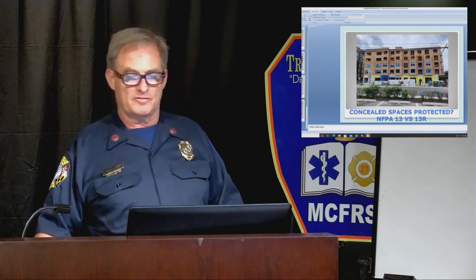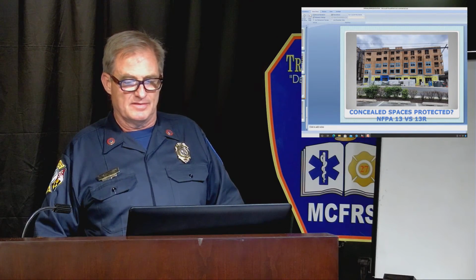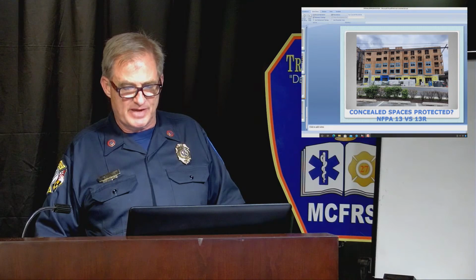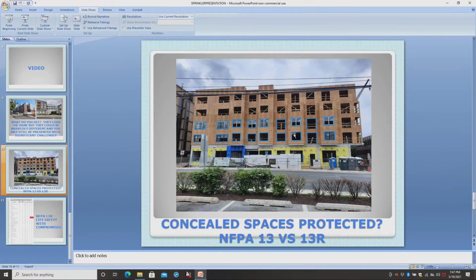Okay, so let's go back and look at our wood building. If we were to roll up to this building, the floor ceiling space across here would not be sprinklered. It would not have sprinklers. The floor ceiling space here would not have sprinklers, and here, and here, and if we had a peaked roof and an attic, we would not have sprinklers there. So the 13R sprinklers have been very effective.